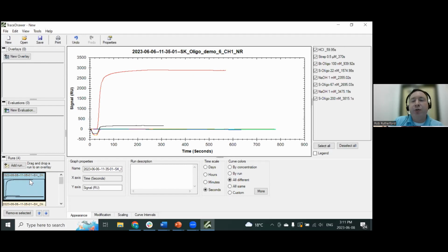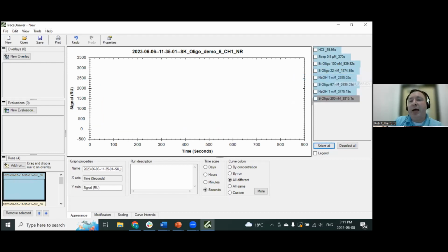I'm then going to go to my channel 1 responses only. So you can see on the right-hand side, we have all of the injections that took place throughout the course of the entire test. And you have the option, you can select all of them. You can select individual ones if you'd like to highlight them or make them a little bit more bold. What I like to do is for my first check, I select them all and then right-click Hide Selected Curves.